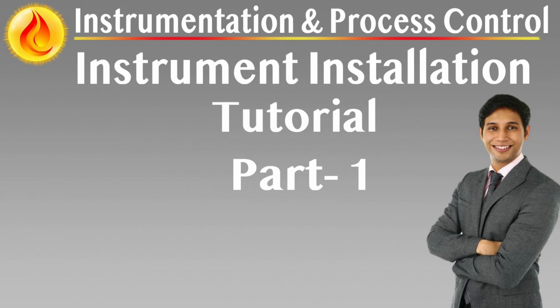Remote versus direct mounting, configuration principles. Two principal design philosophies are employed: remote mounting and direct mounting. Remote mounting relies on a modular platform allowing for optimal access, integration of heating elements, in situ calibration, and reliable impulse line routing. Conversely, direct mounting reduces component count by integrating instrument, manifold, and isolation valve into a compact assembly mounted directly onto the process connection. While direct mounting reduces installation labor and costs, it introduces greater stress and thermal exposure to the instrumentation.